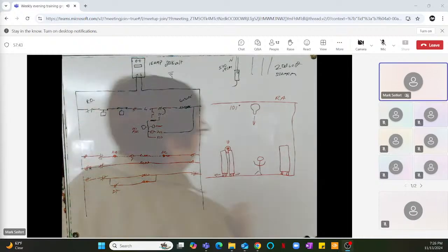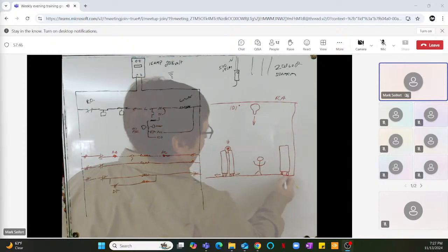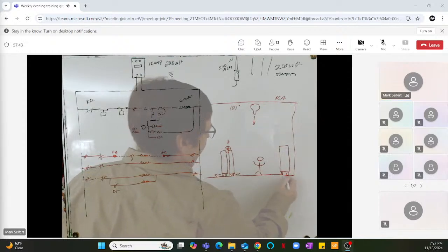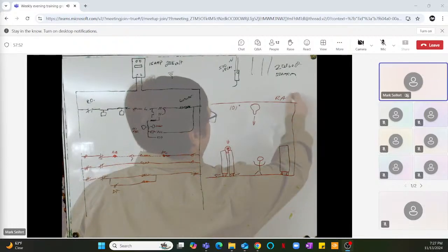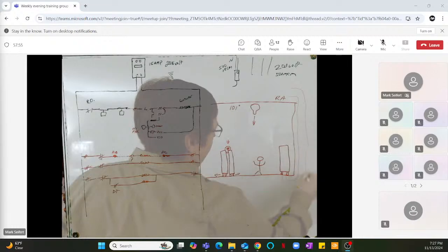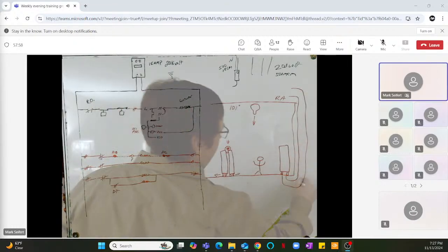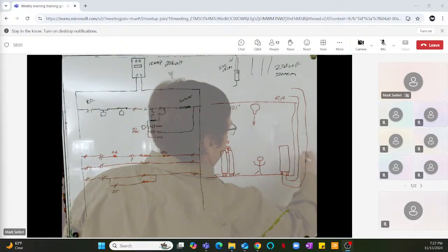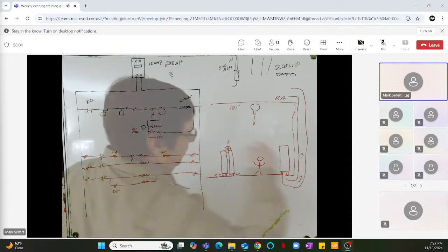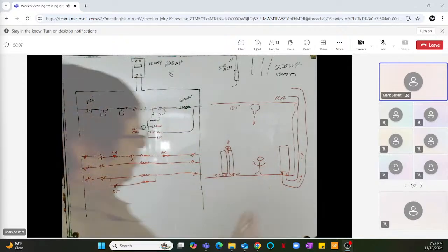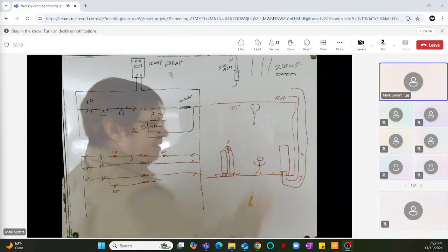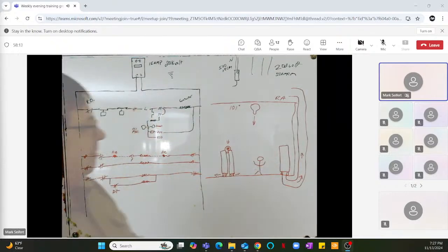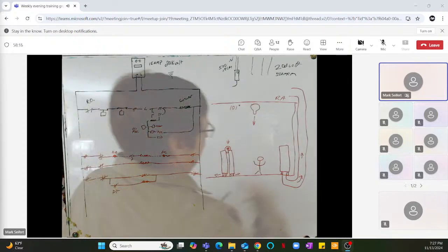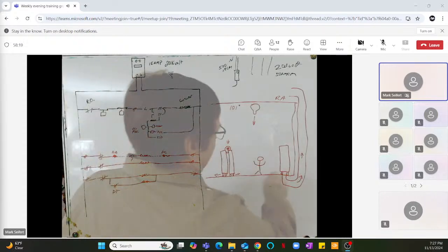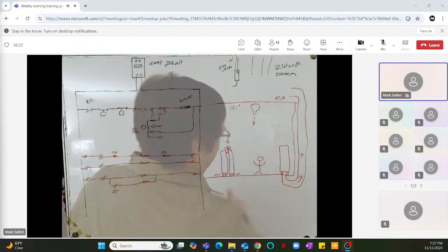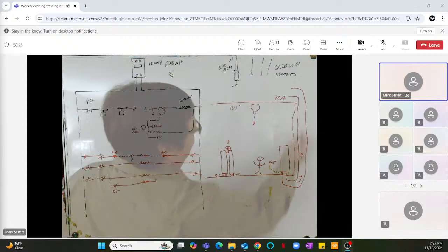However, we have these things called undercase returns, where the return air comes from under the case. Keep this in mind if you've got a store. If somebody's come in and done a remodel and you've got undercase returns and they've blocked the entire toe kicks with brand new toe kicks with no slots in them, let us know. These toe kicks have to be slotted so that the air that's 60 degrees here can go through and down and up into the air handler.